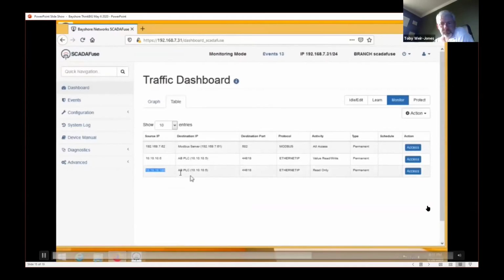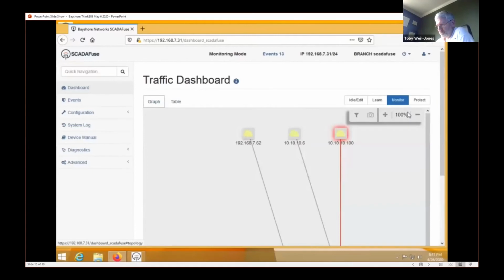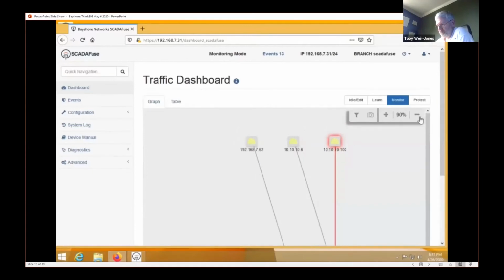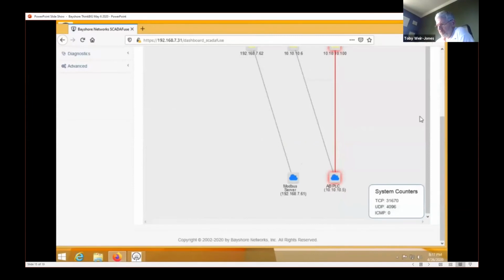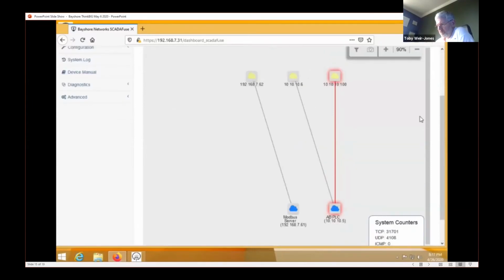It only used read operations in its function codes for Ethernet IP, but that's what we've decided to accept going forward. We can also look at the graphical representation and see that our Allen Bradley PLC now has two different sources permitted to talk to it, 10.6 and 10.100. Both are permitted, but the red indication shows there are unacknowledged additional events between that particular source and the protected asset.